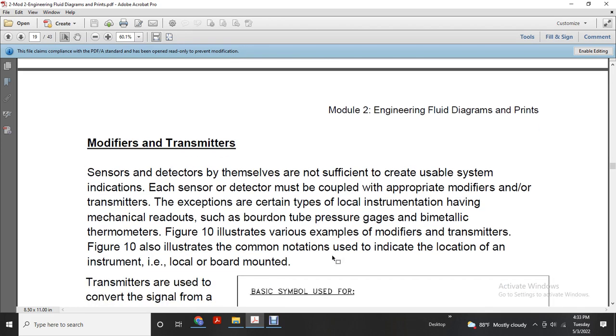Modifier and transmitter. A sensor or detector by itself is not sufficient to create a usable system, which means each sensor or detector must be coupled with an appropriate modifier or transmitter, with some exceptions. Certain types of local instruments have a mechanical readout, for example the Bourdon tube pressure gauge and the bimetallic thermometer. Figure 9 illustrates various examples of a modifier and transmitter.